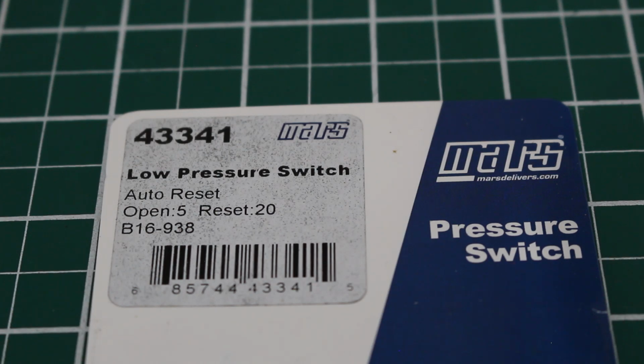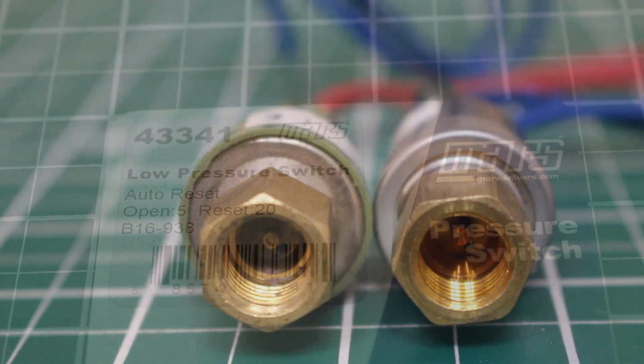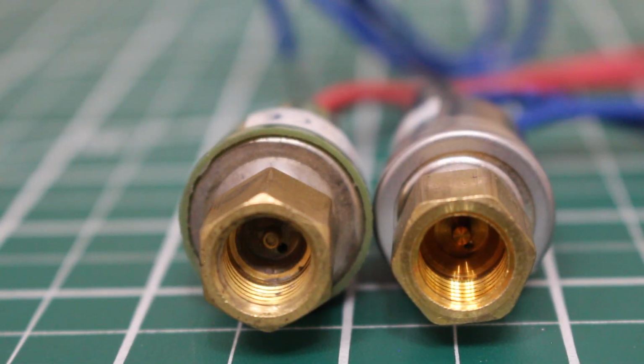It has an automatic reset, so the switch will open if the pressure reaches 5 psi, and it will close or reset when the pressure reaches 20 psi. When we take a closer look at our pressure controls, we can see we have a brass body and it's a female threaded connection. This will get attached to our pressure testing points on either our high and or low side of the system. If we take an even closer look inside, we can see that there's a depressor where a Schrader valve will be in the equation.